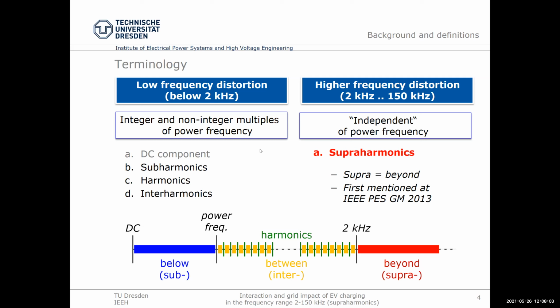On the other hand, if we look at the 2 to 150 kilohertz range, the emission, which is the switching frequency and its harmonics of the devices, is normally independent of the power frequency. Which means we do not talk about multiples here. Anyway, the multiples would be rather high. We talk here about frequency, strictly speaking, frequency bands.